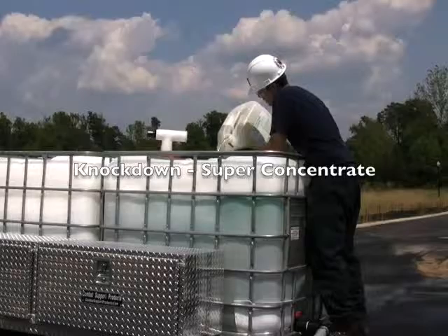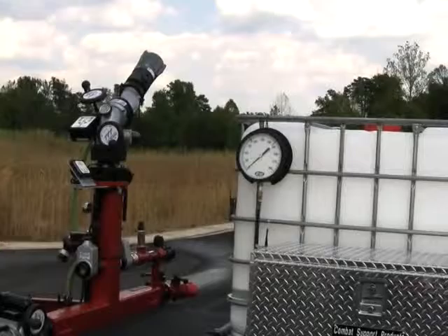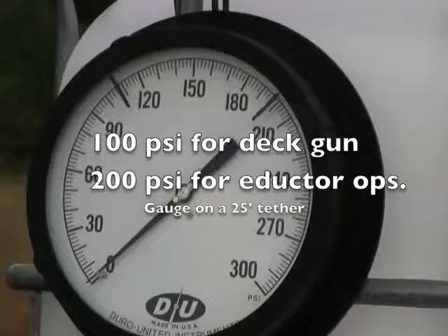What we're going to do now is just add some knockdown. That's National Foam's super concentrated class A foam. It actually makes excellent training foam when you dilute it about five or six times with water. This pressure gauge here is marked at 100 PSI and at 200 PSI. 100 PSI is the pressure that we operate the deck gun at, and 200 PSI is the pressure at which we operate the foam eductors. More on that later.